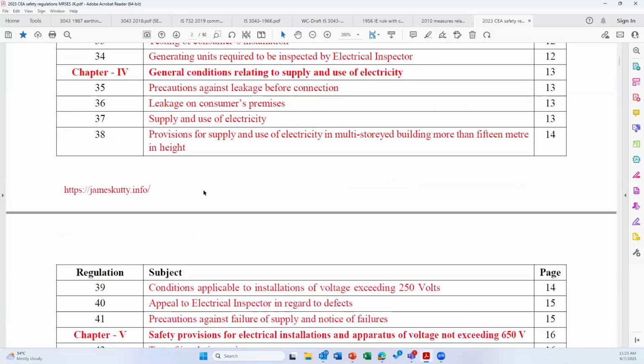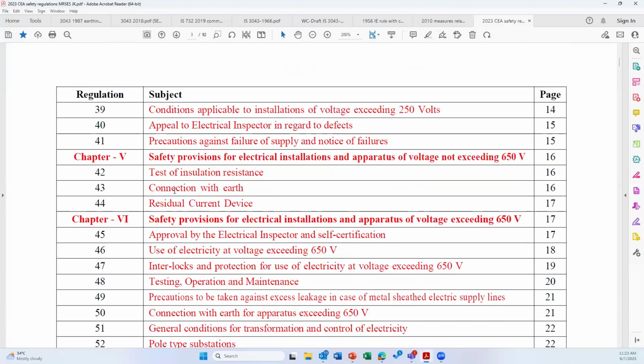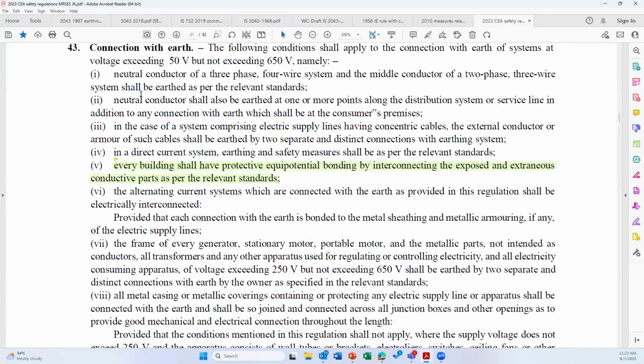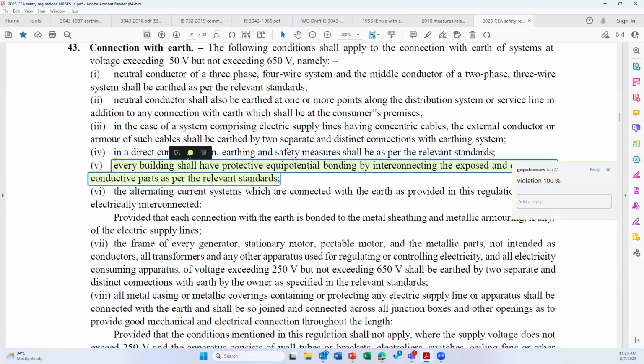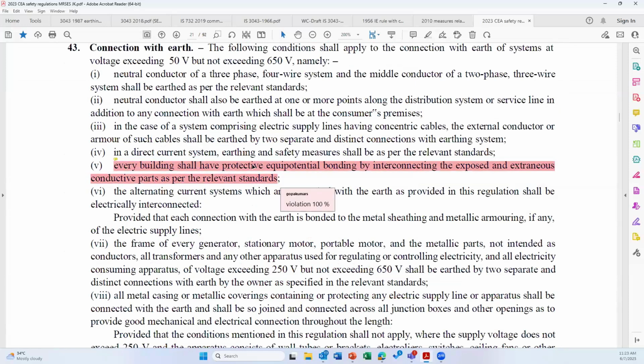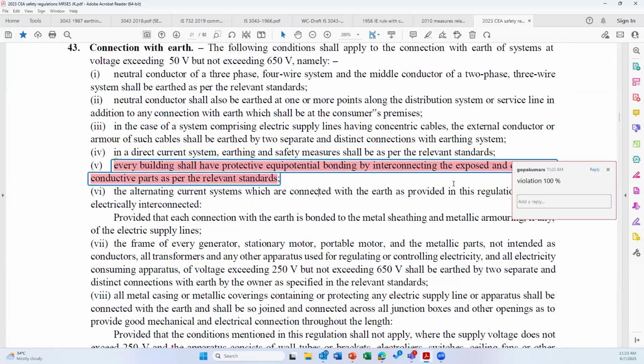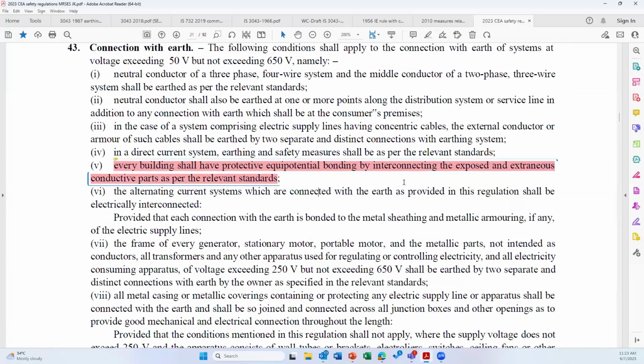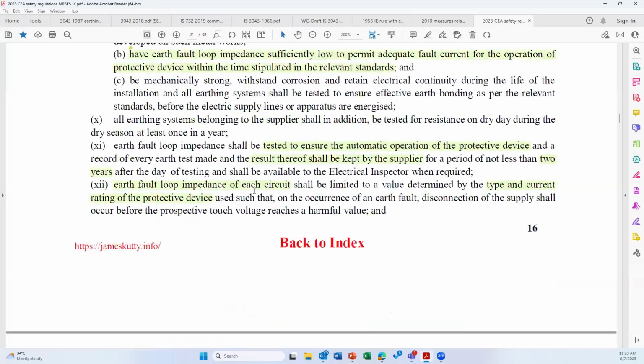Regulation number 43, earthing for low voltage up to 650 volt. What we should do, you can see here in this highlighted part. Every building shall have protective equipotential bonding by interconnecting exposed and extraneous conductive parts as per the relevant standard. So here the relevant standard is IS 3043.